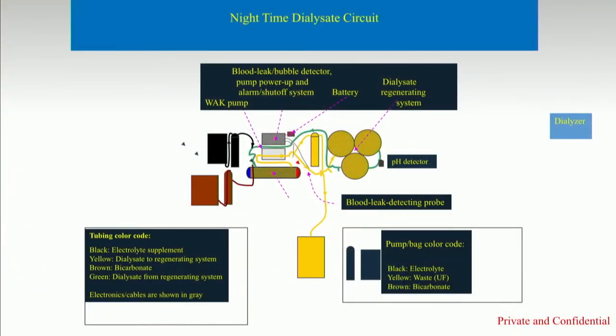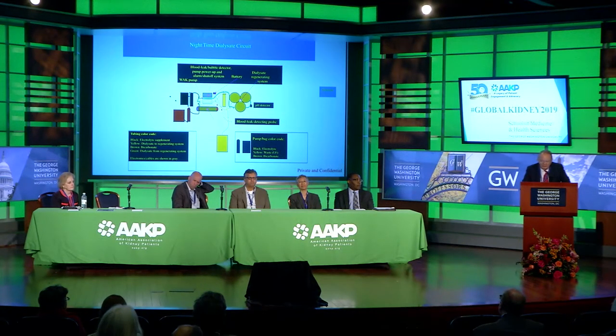What we reasoned is that there are tasks the WAK performs over 24 hours that must be performed over 24 hours. For instance, physiological removal of fluid over a 24-hour period. If you want to remove too much fluid too fast, you get cramps and hemodynamic issues, so it has to be continuously removed. Uremic toxins—the whole group of toxins shown to be noxious, and I'll talk about that a bit if we have time—need to be removed over 24 hours.